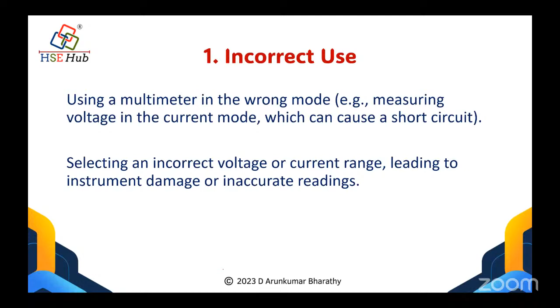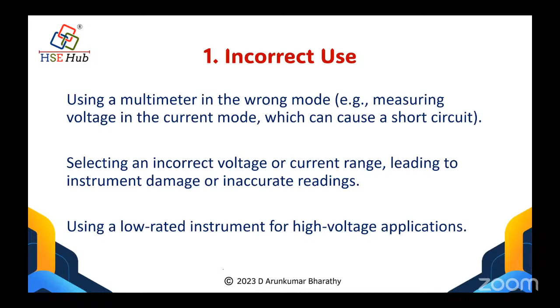A low rated instrument used for a high voltage application can also blast. I'm going to show some other videos where the instrument itself blasts. So in spite of having the right, certified equipment, if it's not used correctly on the field, in terms of what we are measuring, what selection to make, and what accessories to use, incorrect use means no one can be saved despite all the safety precautions and systems.